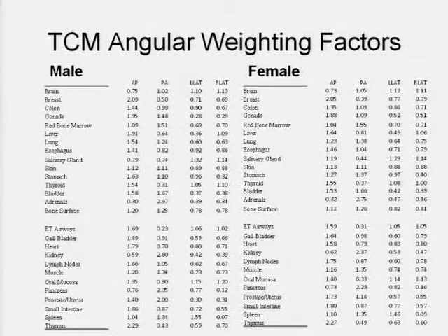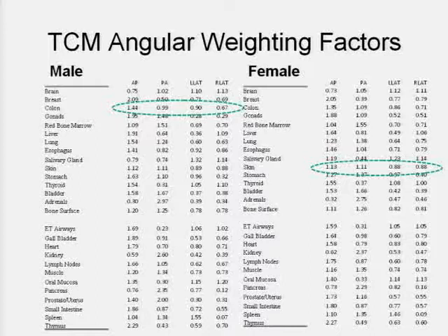But just as an example, and I don't expect you to look at all these numbers, this was an attempt at trying to understand the sensitivity of organs to beam direction. And we know that some we would expect to see. This is essentially looking at the sensitivity, the relative contribution from each direction. Some don't vary that much with position, not a whole lot of variation. For these, we would expect the tube current modulation that's applied is not going to have a significant impact on dose.